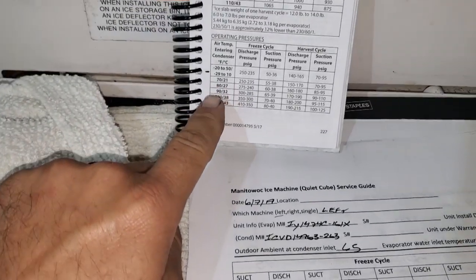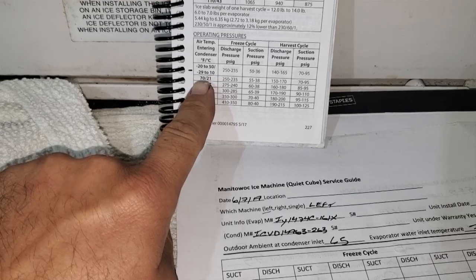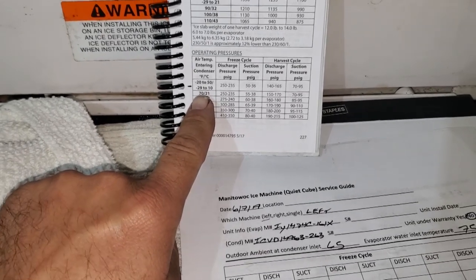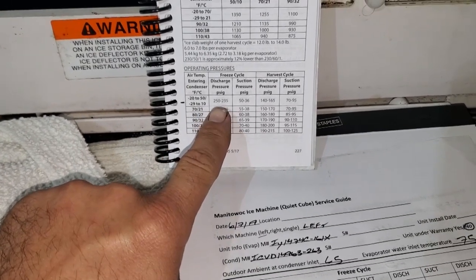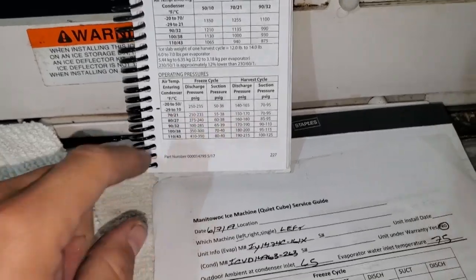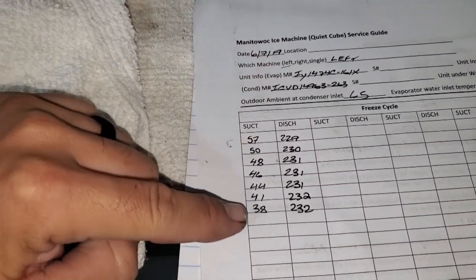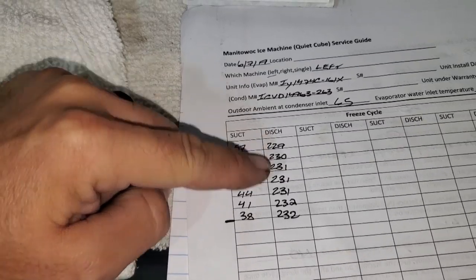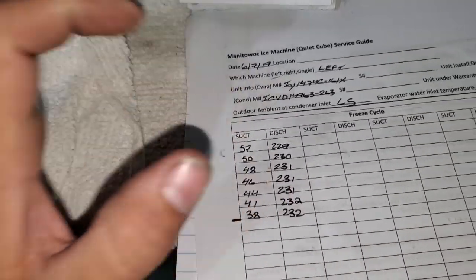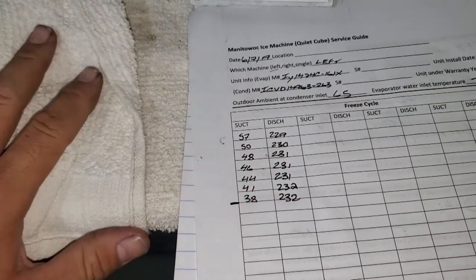So, analyzing my pressures, we should be using this bracket right here because it's 65 degrees outside, so we're below 70. So 250 to 235, and 50 to 36, so 57 to 38, 230 to 232. So we're a little low on the head pressure, but that's a common theme on these Manitowoc ice machines.